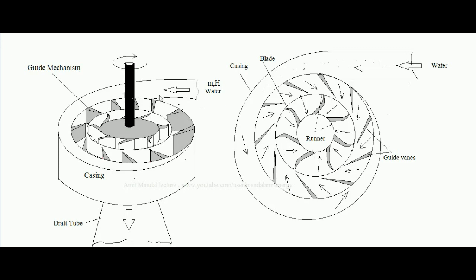Regarding the flow direction of a Francis turbine: initially the flow is radially inward — water moves toward the center in the radial direction. After passing through the runner, water collects at the center and then moves in the axial direction. So initially water moves radially and ultimately axially, which is why the Francis turbine is also called a mixed flow machine.